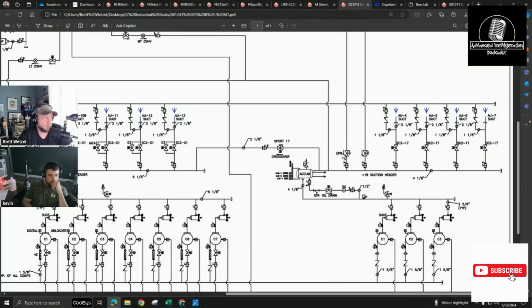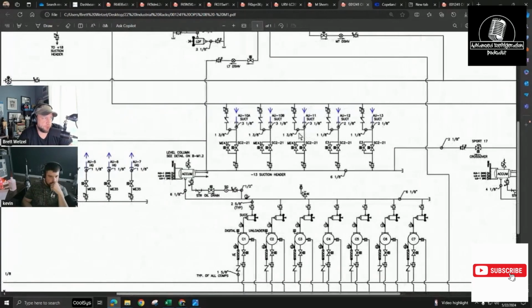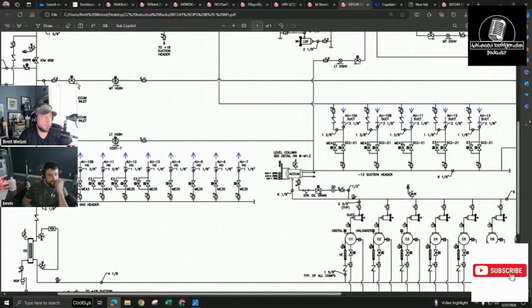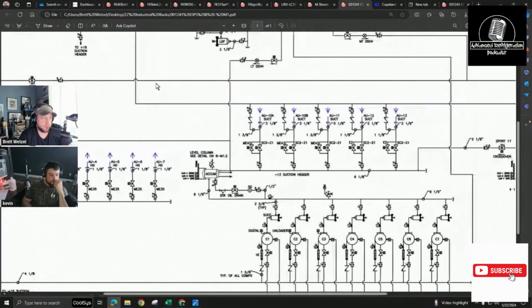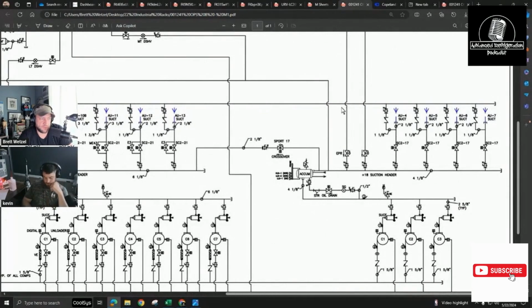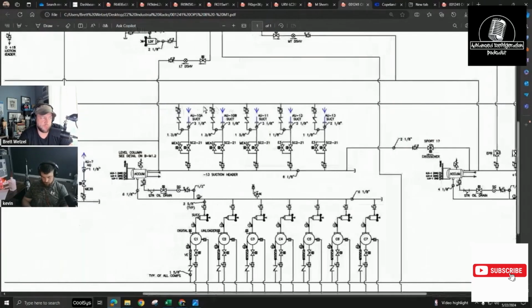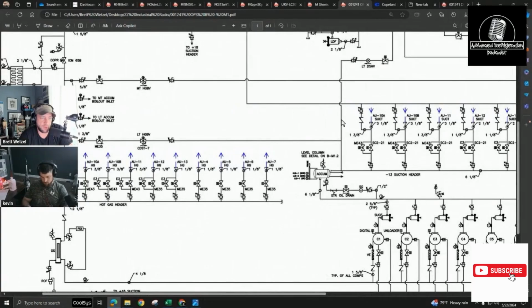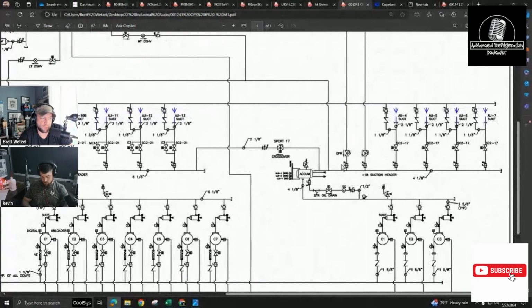And on this rack, it looks like they also have a hot gas bypass valve. This would probably be the next thing it uses to combat if the load starts dropping off or the suction pressure starts delving down too low. And if it gets any worse, where it still can't keep loaded up enough with this hot gas bypass valve, then you have this load shedding valve to essentially take its place.